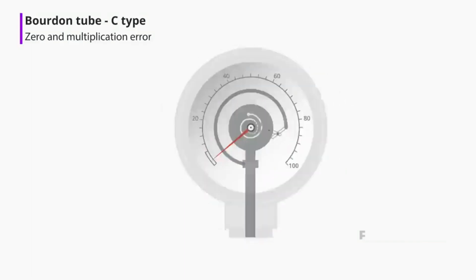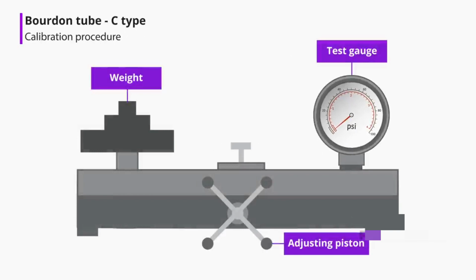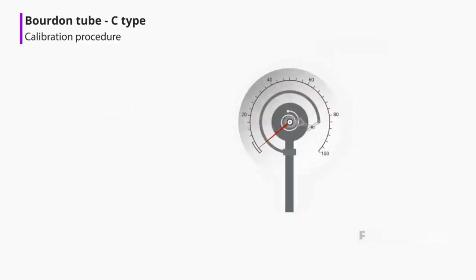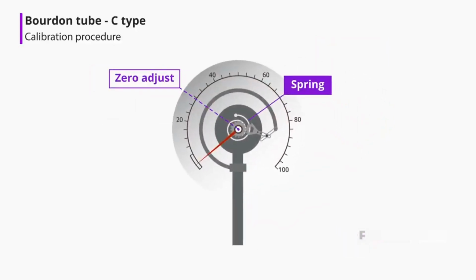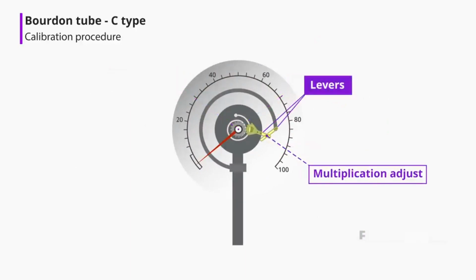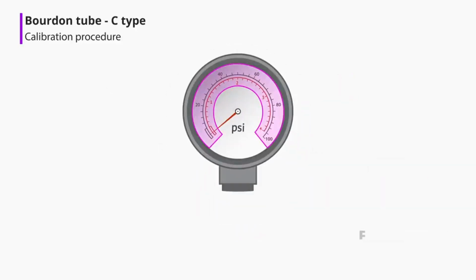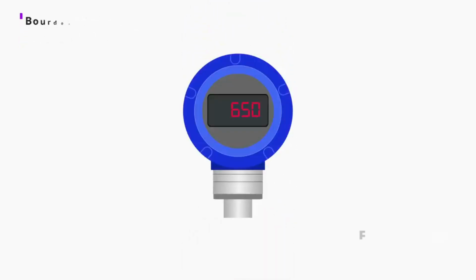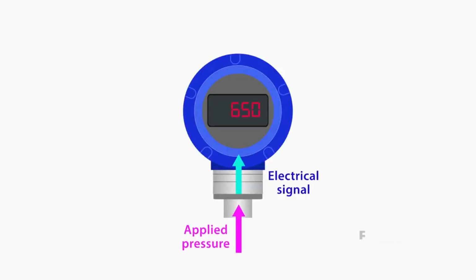Calibration is normally done on a workbench using a pressure sourcing device, such as a deadweight tester. Zero error is corrected by repositioning the pointer on the shaft or by changing the tension in the spring. Multiplication error is corrected by changing the length of the levers. Generally speaking, a mechanical pressure gauge will have an analog readout or analog scale. Many of today's pressure gauges are equipped with a pressure transducer that converts pressure into an electrical signal. This electrical signal is then often used to operate a digital display.